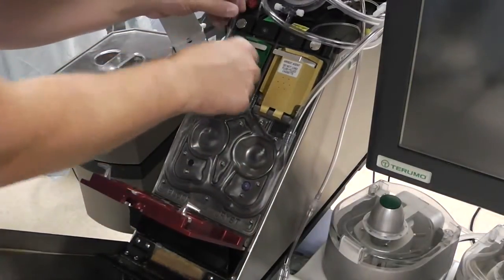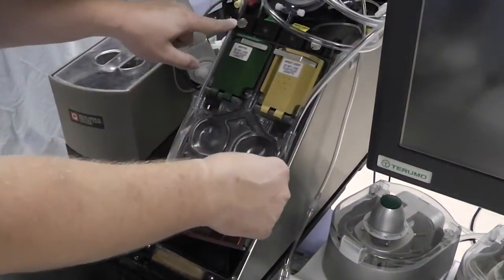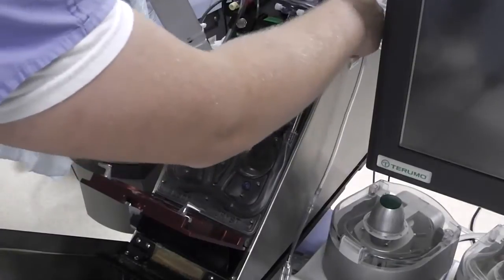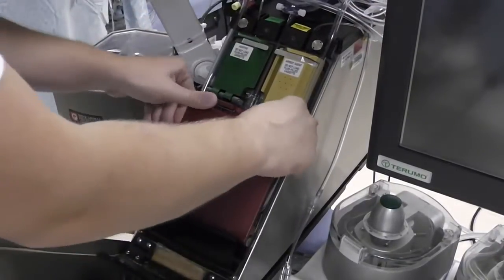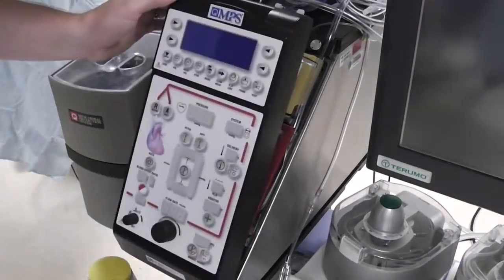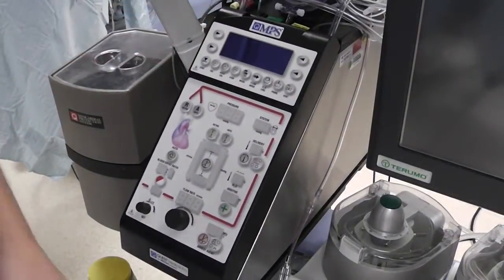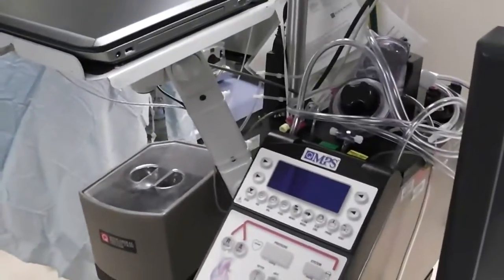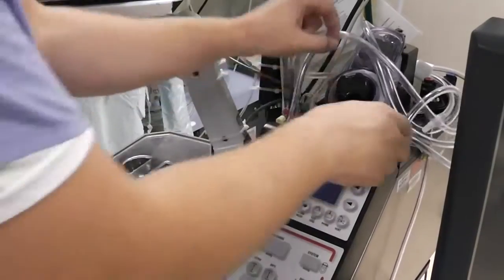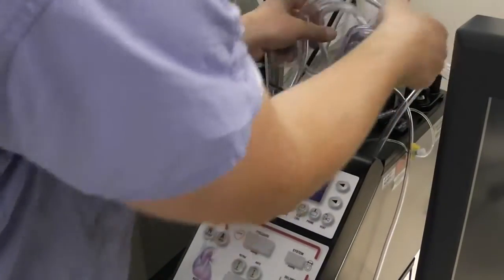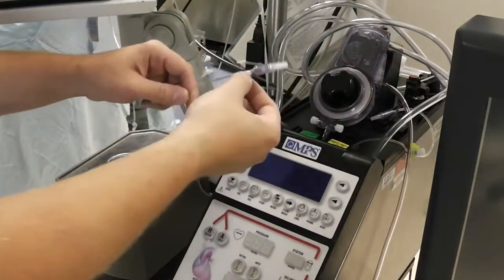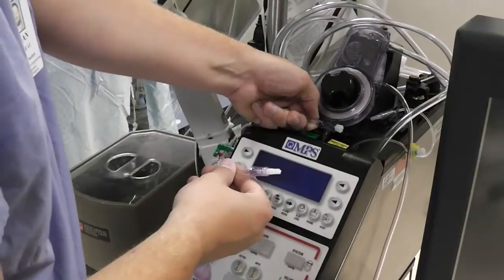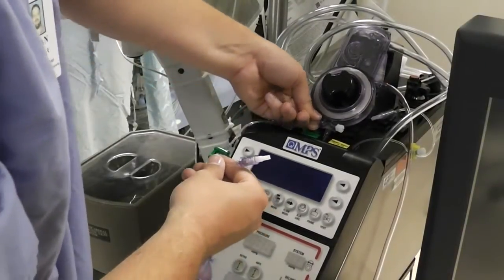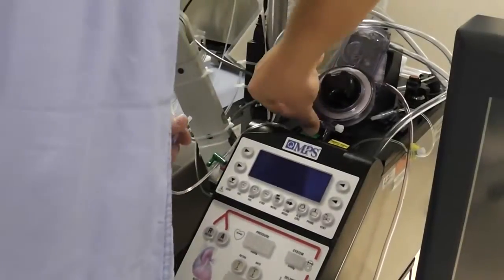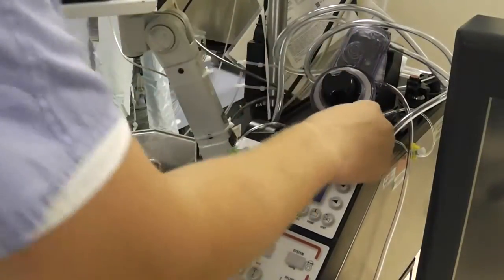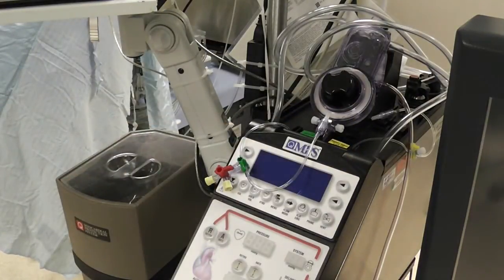Alright, coming up, we're going to seat these hoses into the slots at the top of the Quest, and then close this door. And at this point now we can close the front cover, and make the rest of the Quest connections. So I'm going to kind of get these lines out of the way. We're going to take our green side, remove the cap on the left, and sometimes these are really tight. Usually they come right off, but sometimes they're really tight and you have to actually get a clamp. So let me do that.